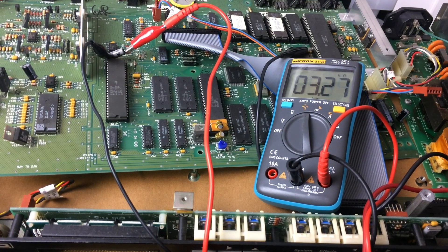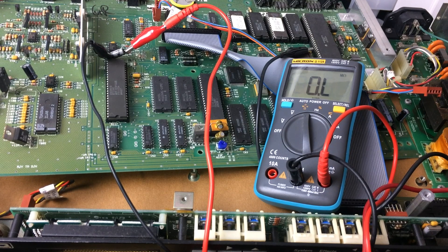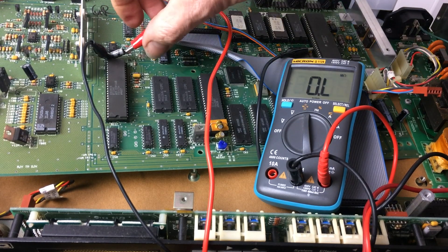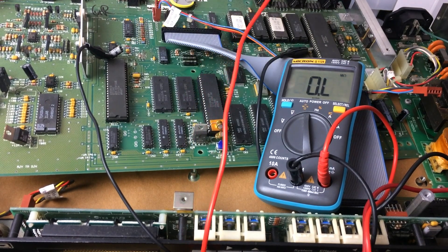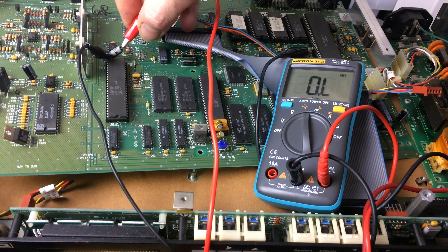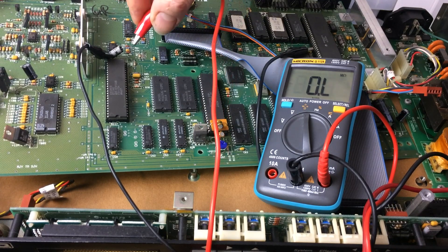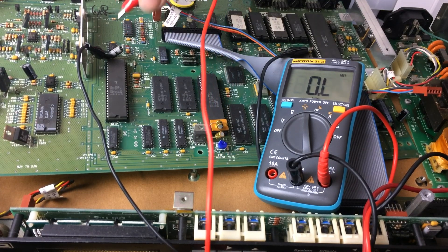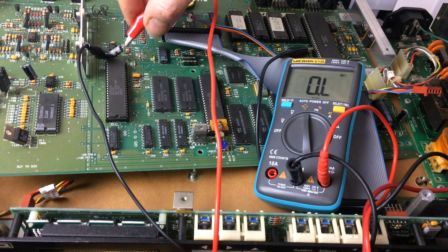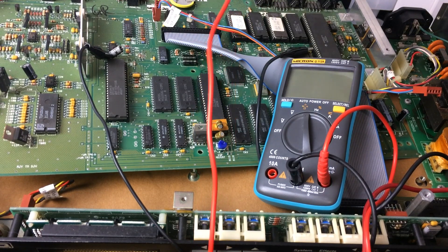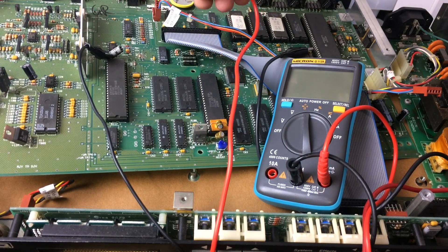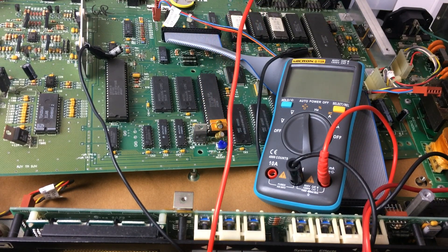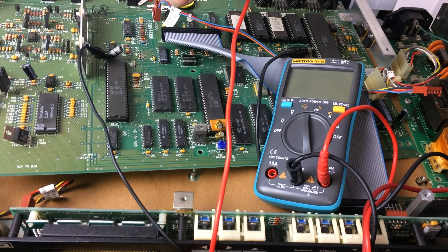So let's go. Here it goes increasing in resistance. Bang. Overload. So now that that's reached overload, the capacitor is charged. And when I again take my connector off and try to retest it, it won't let me test it. It will look like it's open circuit. So that's a really important thing about capacitors to check them properly.